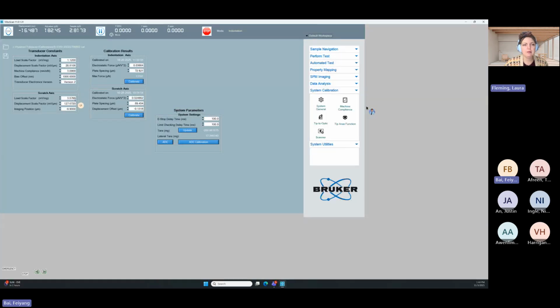Okay, it's there. Yep. So these are true. These are always the numbers you're going to use, this 1.12 and this 20.8108. Those are calibrated at the factory. The machine compliance is dependent upon the system and will change from system to system, and even where it's installed can change it slightly. So that is a user-updated or service-engineer-updated field. That's why it's not in the sheet.